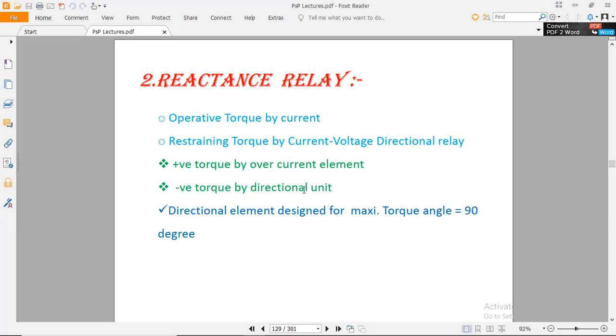So we discussed the concept of the reactance relay, and we already discussed the positive torque by the overcurrent element and negative torque by the directional unit. The directional element is designed for a maximum torque angle of 90 degrees, at which the maximum rotation is performed, and by restoring it again reaches 0 degrees of angle.